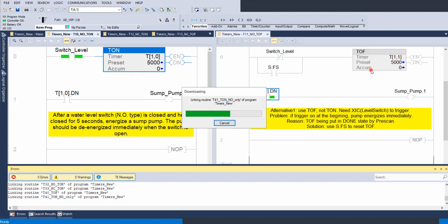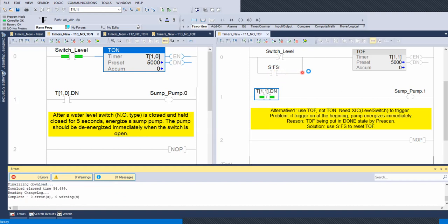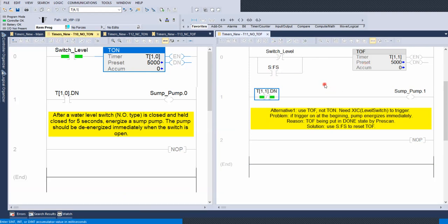Right. So if you remember, we talked about the off delay timer. Some specifications ask the user to turn on the off delay at the beginning for at least maybe a few seconds in order to make the timer operate appropriately. So that's the equivalent in the PLC. We just use the first scan as the trigger to reset it, right? So now you can see here it's in program mode, right? Trigger is on and pump is off, right? This is the modification we have.